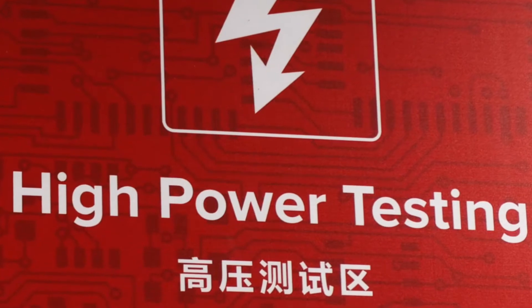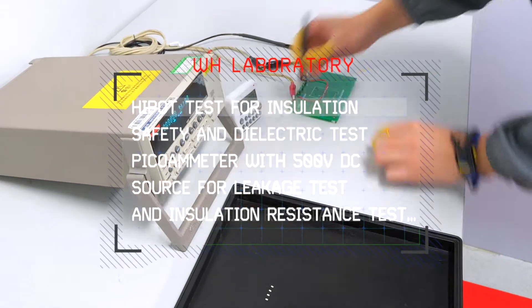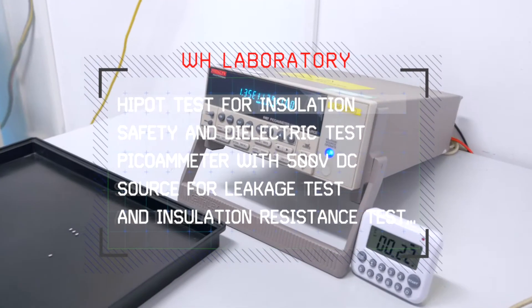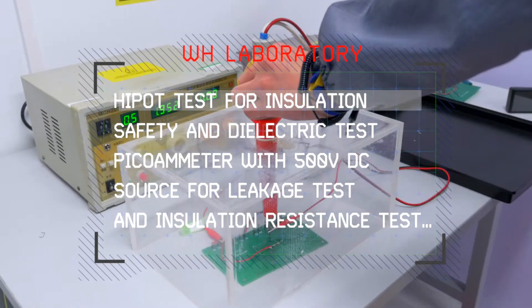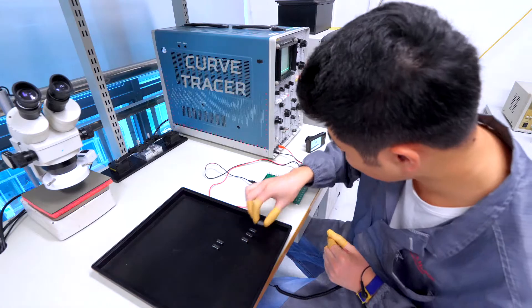This area is where we're doing all of our high voltage testing. We put high voltage into it to see if the device will actually crack — this is called dielectric withstanding voltage or resistance to voltage. That device there is a curve tracer.